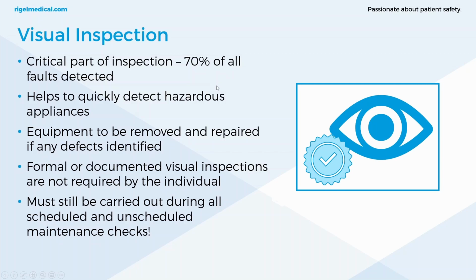Visual inspection. These help to identify any hazardous appliances in the healthcare facility pretty quickly. They form a critical part of the general safety inspections during the functional life of medical equipment. And this is because 70% of all faults are detected during this visual inspection. Now, it's not just biomeds that need to be aware of this, it's all staff that are using the equipment. They should be observant of the condition of the equipment they use, and if any faults appear, that should prompt them to send it into the workshop for repair, and it should be removed from service altogether. Now, NFPA 99 doesn't state any formal or documented visual inspections by the individual, but a checklist is always handy to have in the workshop for you to follow, but it's general common sense. However, I've seen it in workshops where they've got a step-by-step guide of what you need to look out for.